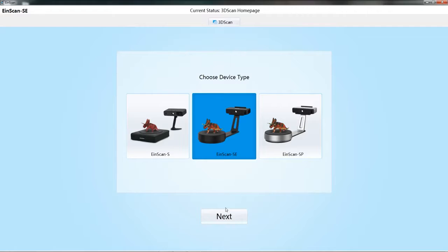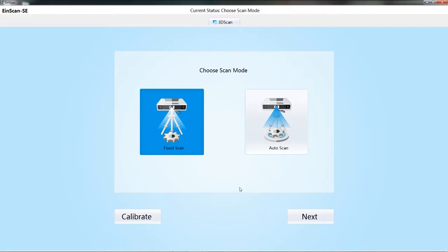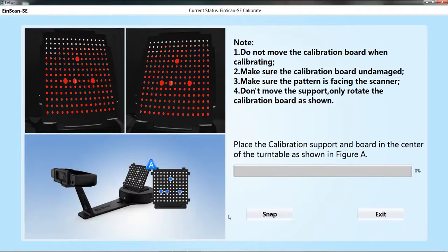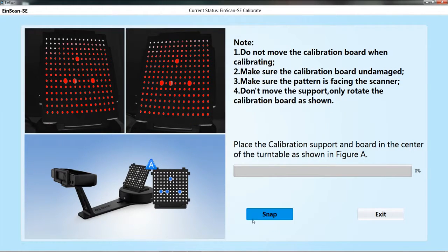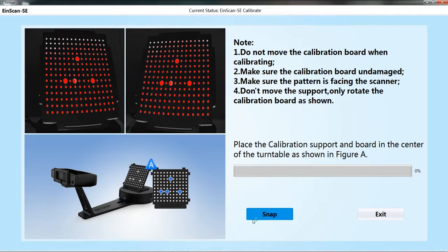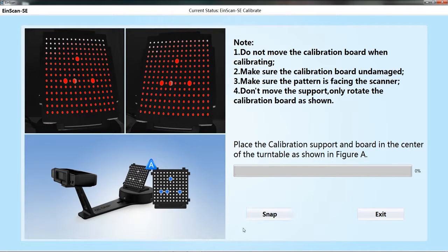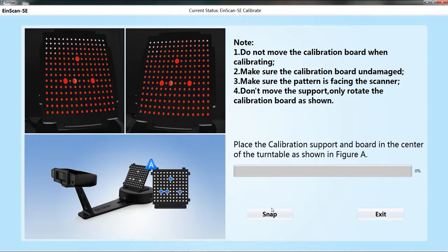When the scanner is used for the first time or the scanning result is poor, calibration is needed. Place the calibration board as diagrammed on the calibration interface. Click the snap button to start collecting the calibration board information. The entire calibration needs three collections of calibration board.